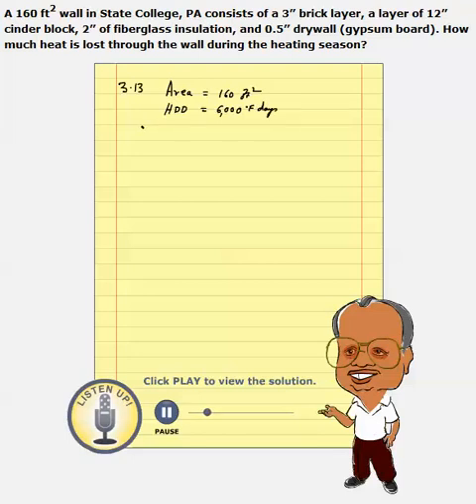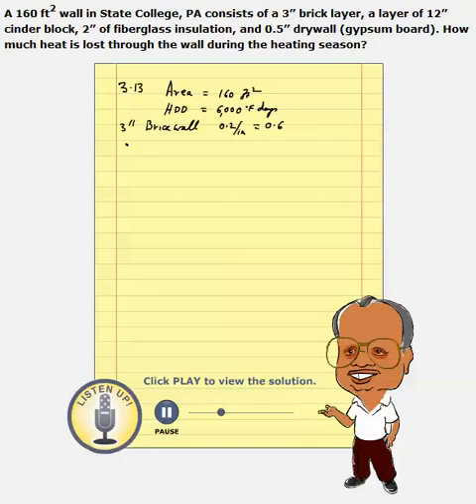Now we need R. The wall appears to consist of four layers. One is the brick wall, and this brick wall is three inches thick, and each inch gives us an R value of 0.2, so three inches would offer a 0.6 R value. And similarly, 12 inches of cinder block — each inch has an R value of 1.89, therefore 12 inches would provide us 22.68.